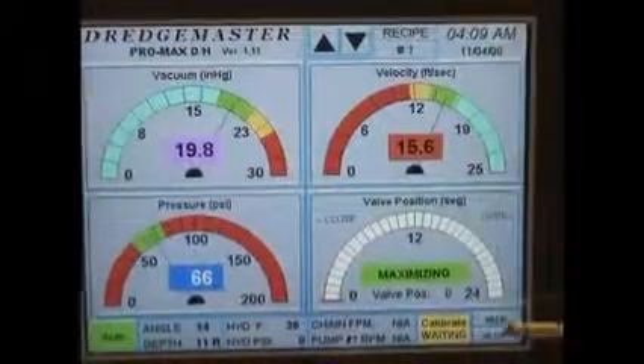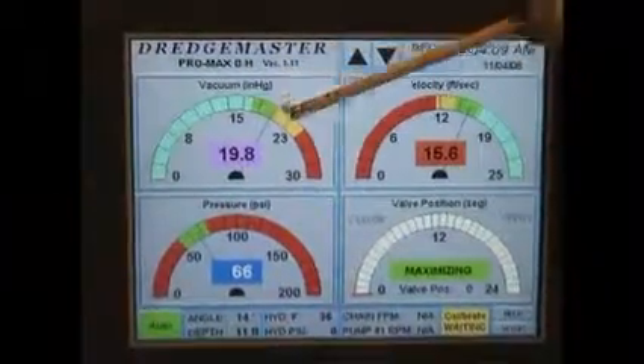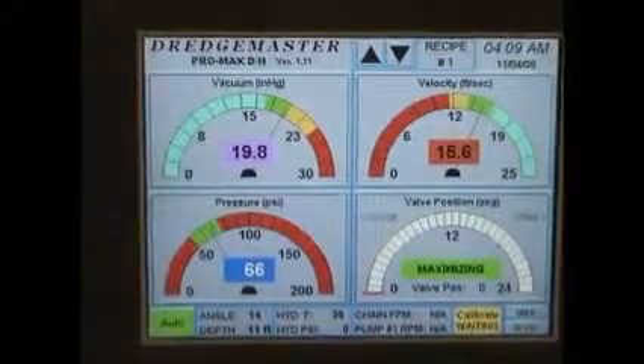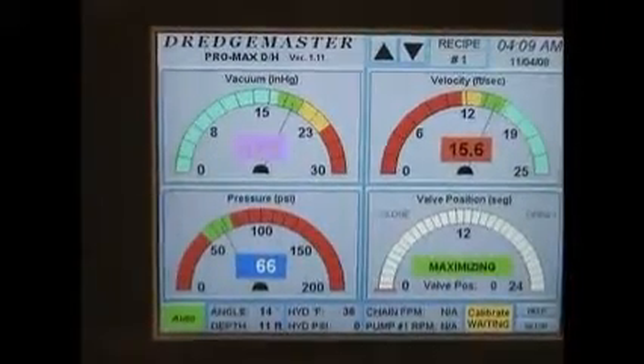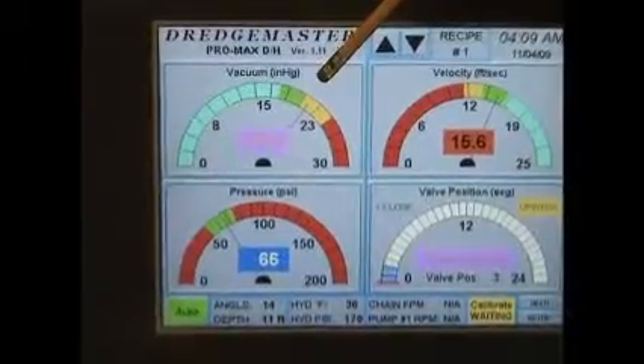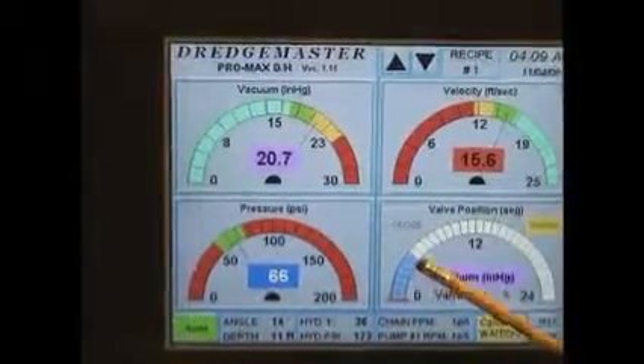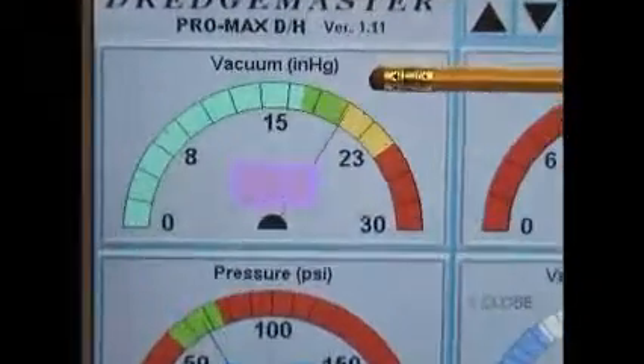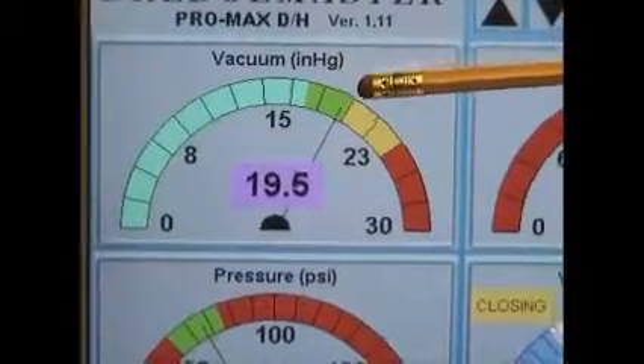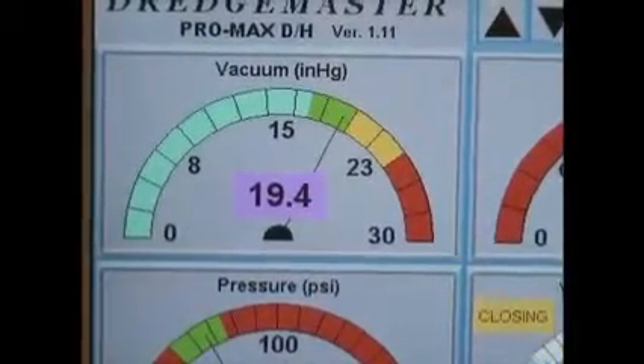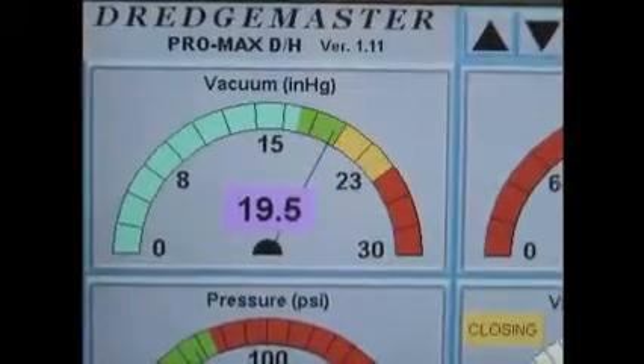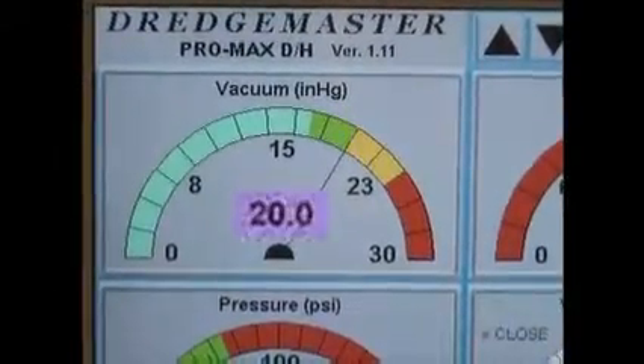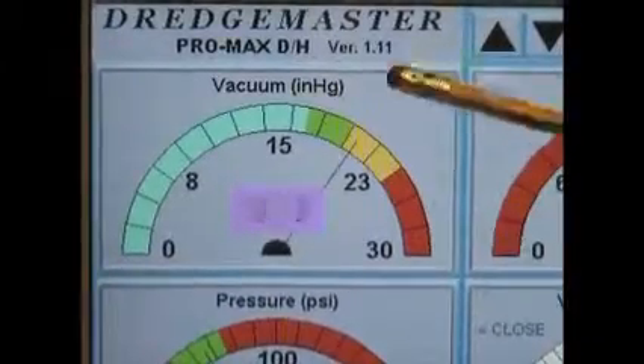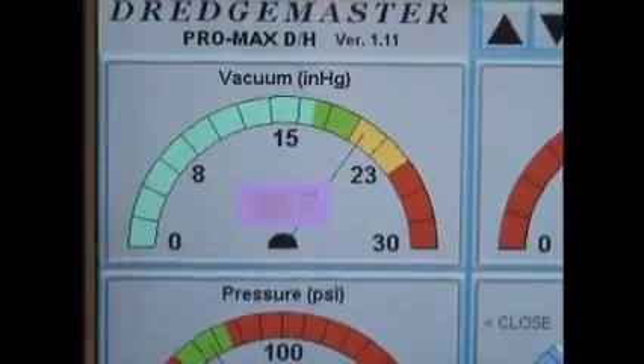We're going to go back to our main gauge by touching the main button, and boom, you can see how all our colors just changed. So now, for the valve to start opening up, we have to get to 20 inches of vacuum. Once we get less than 20 inches, we're back into our green zone and our valve can start closing itself back down. So this is the set point between our green, which is closing the valve, and the yellow area, which is stepping the valve open.